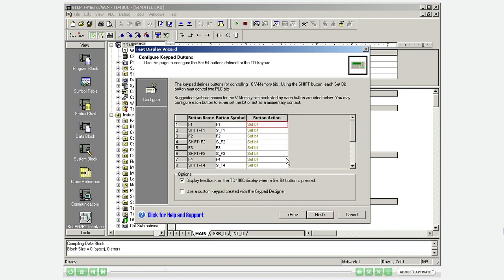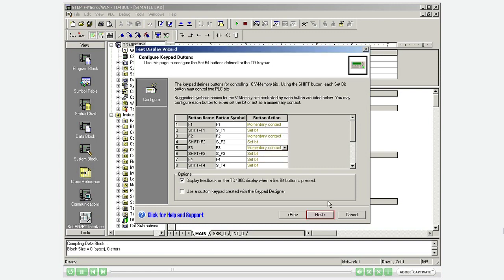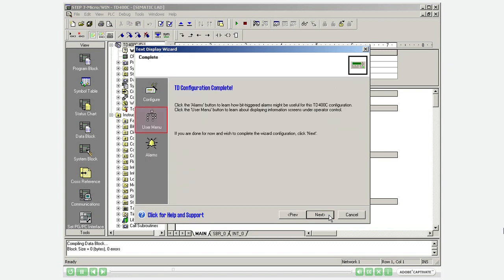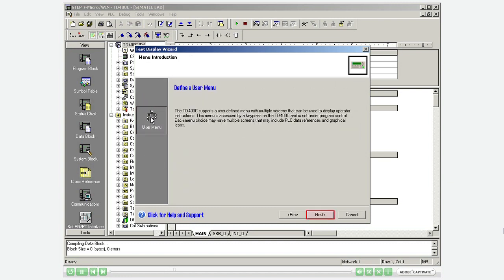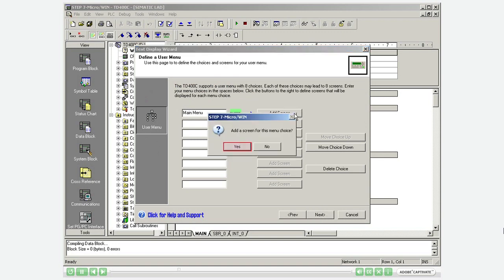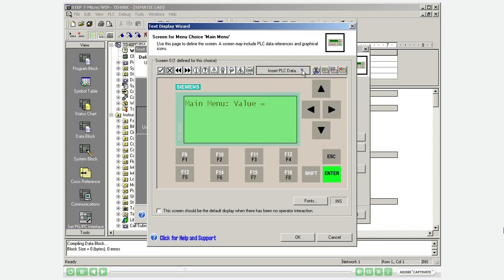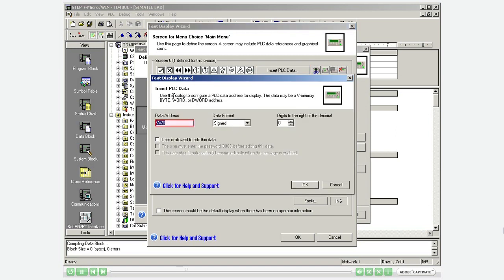Change the actions of the required function keys to momentary contact. Go to the configuration of the user menu. Assign a name for the menu. Add a screen. Label the menu screen according to the task. Insert PLC data to display the variable named value. Select the address for the data such as VW1000.